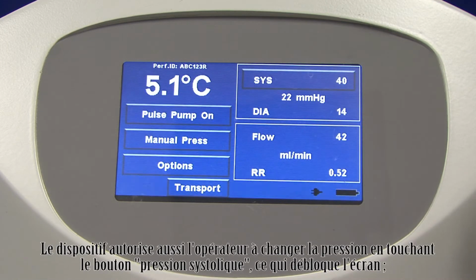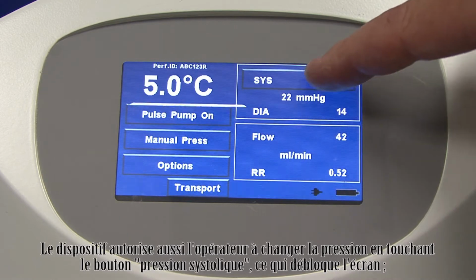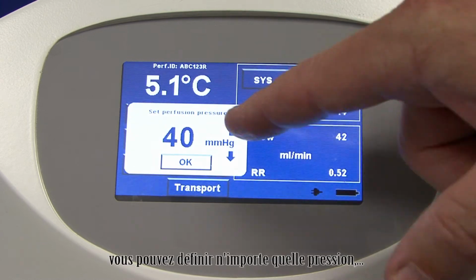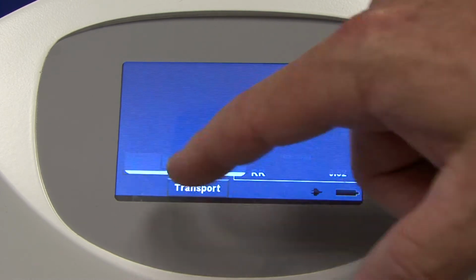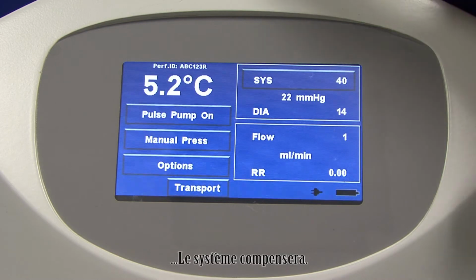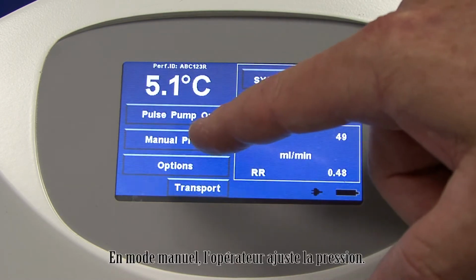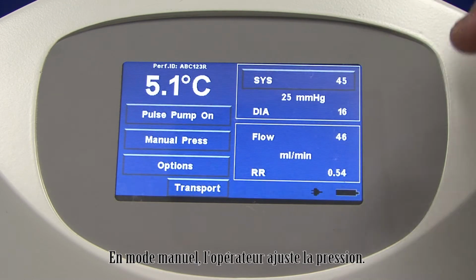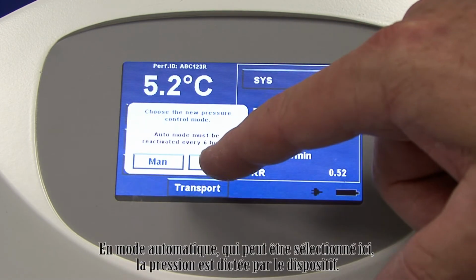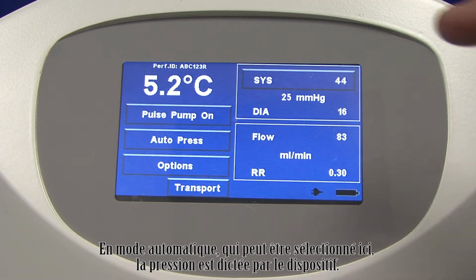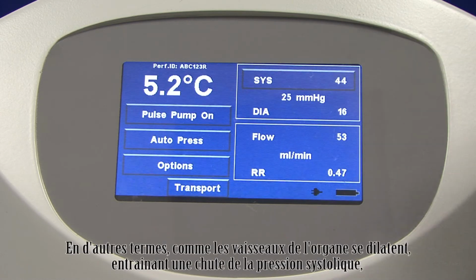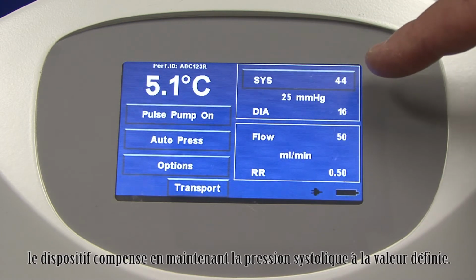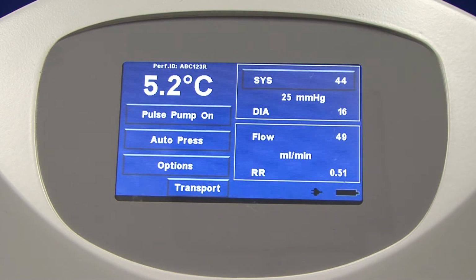The device also allows the operator to change pressure by touching the systolic pressure, which unlocks the screen, and you can move the pressure to any designated pressure, and the system will compensate. In manual mode, the operator adjusts the pressure. In automatic mode, which can be selected here, the pressure is dictated by the device. In other words, as the organ begins to open up and the systolic pressure falls, the device compensates, bringing the pressure back to the set systolic pressure.